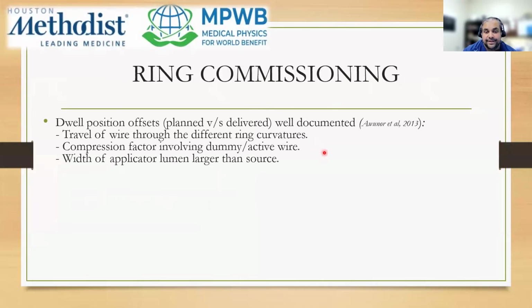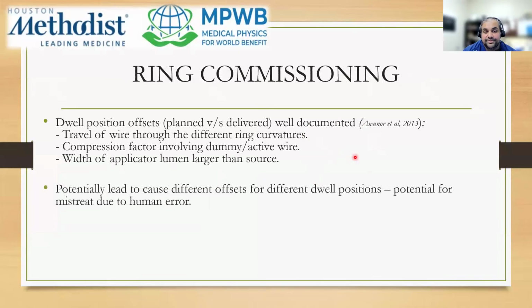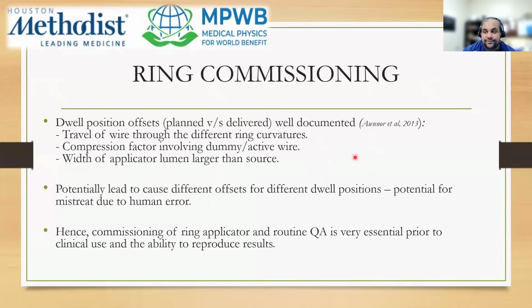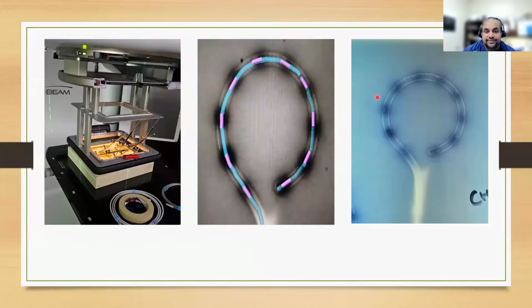Same thing for the ring. Because of its curvature, it's well documented that between your planned and delivered dwell positions there is going to be an offset. So whenever you get a ring applicator, please test it out and ensure that the dwell position that you intend to deliver is what the machine is doing. This is what the setup looks like. I have the rings taped, and these are the X-ray markers in the ring. As soon as I take the image, I then connect it to the remote afterloader and run a test plan.